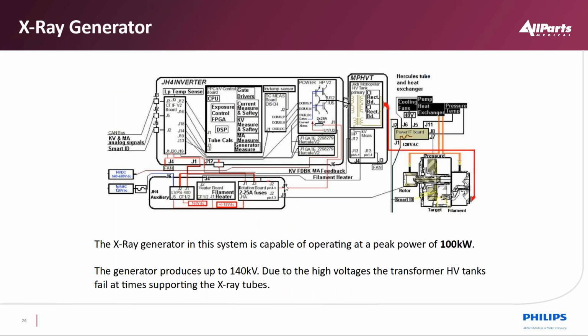So this is an example of VCT's X-ray generator. We're taking line voltage about 700 volts nominal, converting it into AC, and then rectifying that AC with a tuned circuit to give us our voltage up to 140,000 volts. On this tube, it's a single cathode connection with 140 on one cable, and the anode's grounded. But in other scenarios, we have a plus and minus kV that equals 140,000.